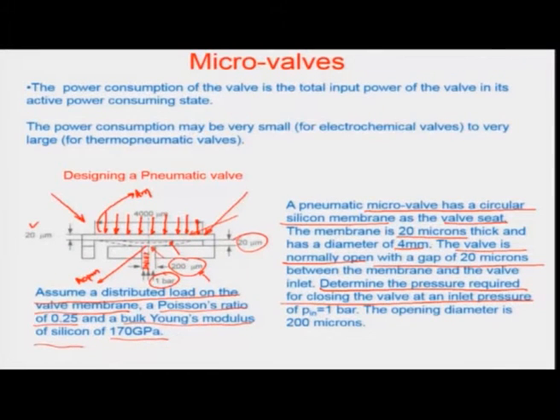In case 1, when actuation begins, we have P_act on one side with membrane area A_m = π·R_m², where R_m is 2 mm radius of the circular valve. This equals the inlet pressure times π·R_m², because at the beginning of actuation the whole inlet pressure is available on the lower side of the membrane — the membrane has not yet deflected or moved.